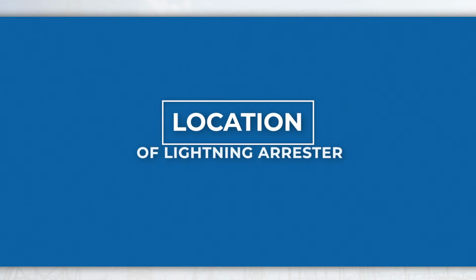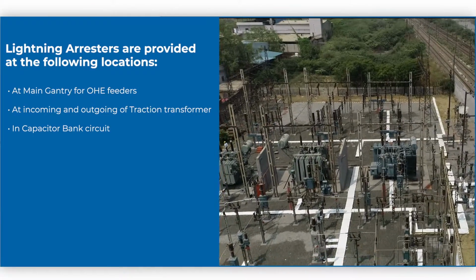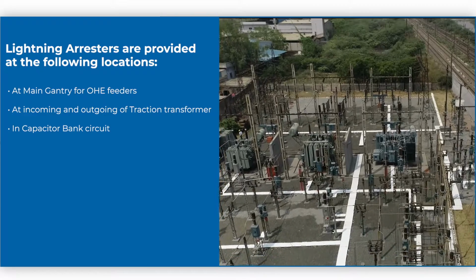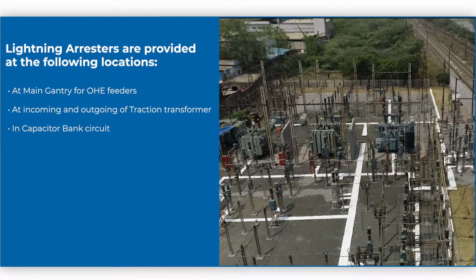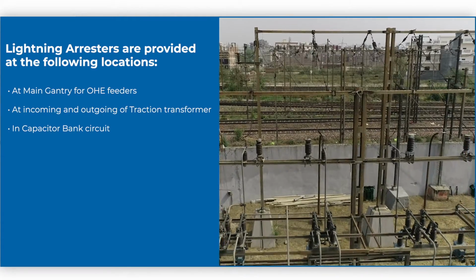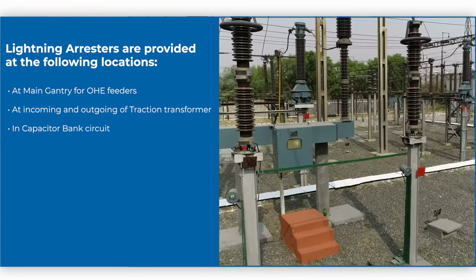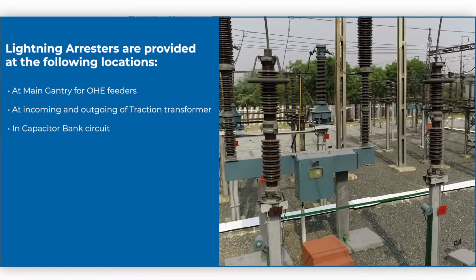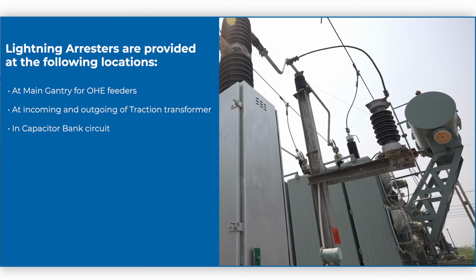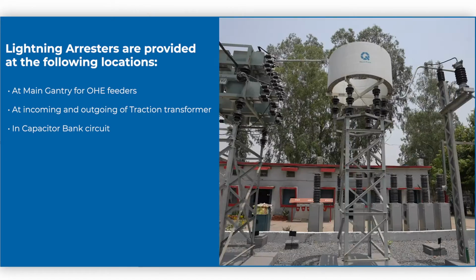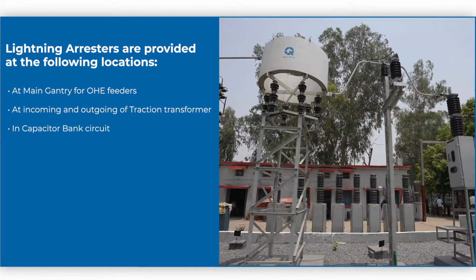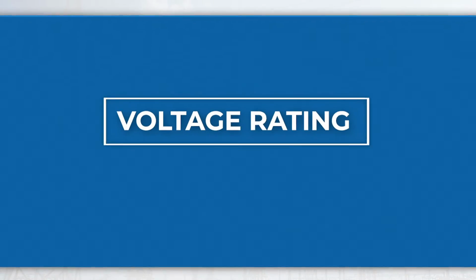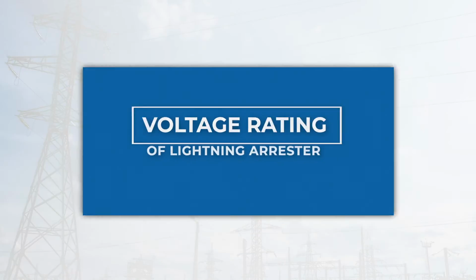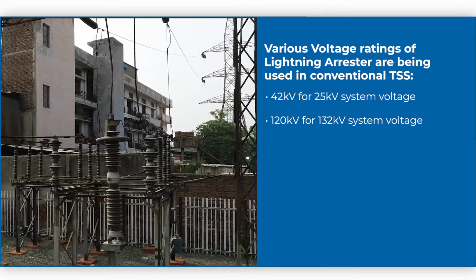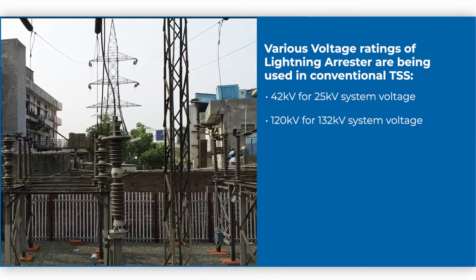Location of lightning arresters. Lightning arresters are provided in TSS at these locations. Main gantry LA with disconnector. HV side LA with grading ring. LV side LA at TR secondary and capacitor bank circuit without disconnector. Voltage rating of lightning arrestor. These lightning arresters are available in various ratings.